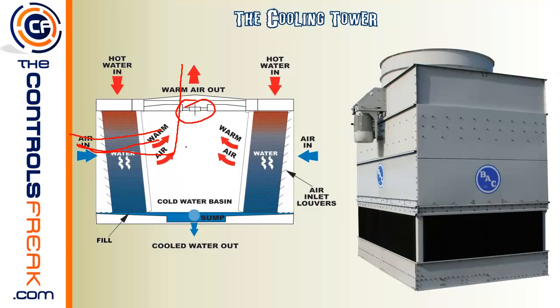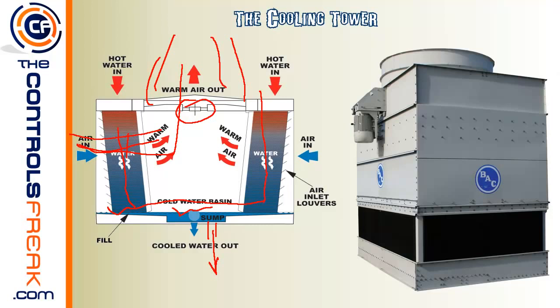Early in the mornings when it's cool out, you'll see big plumes of steam coming out of rooftops — that's exactly what you're seeing, all that hot air coming out the top. As the water falls down it goes from hot to cold. There's usually a cold water basin at the bottom holding one or two feet of water. One pipe returns that cooled water back to the chiller, completing the cycle: hot water comes in at the top, gets cooled down, and gets pumped back toward the central plant to cool down the condenser side.